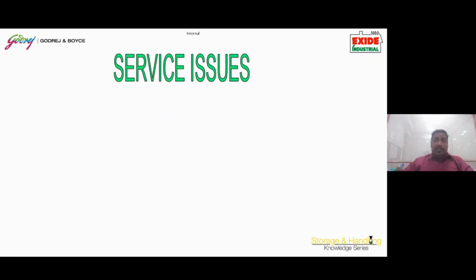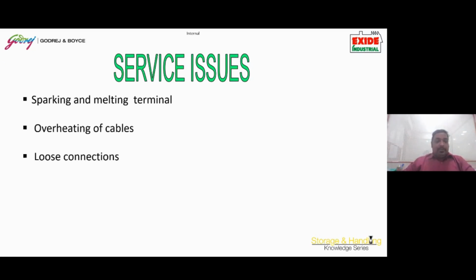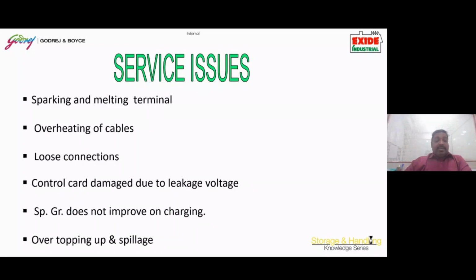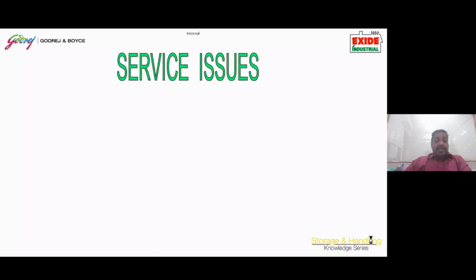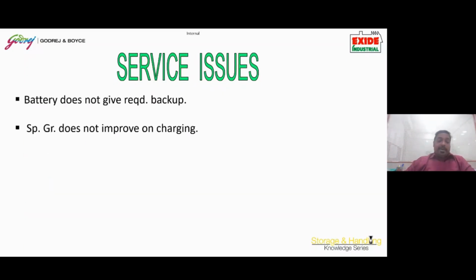And let us find the common failure modes in a battery. What are the service issues that come in a battery? The most common service issues, over the years of my experience and my team's experience, are sparking and melting of the terminal, overheating of cables, loose connections, control card damage due to leakage voltage, the specific gravity not improving on charging, overspilling and spillage, and the battery not giving the required backup.